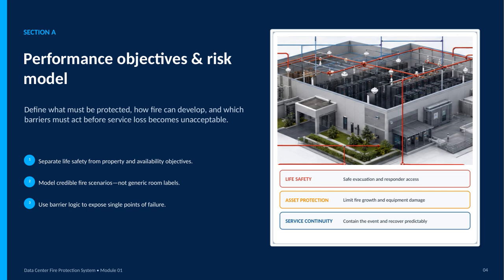The second principle is to model credible fire scenarios, rather than relying on generic labels such as server room or electrical room. The actual scenario determines how fire may develop and which systems are exposed. Finally, barrier logic helps us test the protection strategy. We identify the barriers that must act before service loss becomes unacceptable, then look for single points of failure. In other words, the goal is not simply to install protection, but to understand how each layer contributes, and what happens if one layer does not perform as intended.